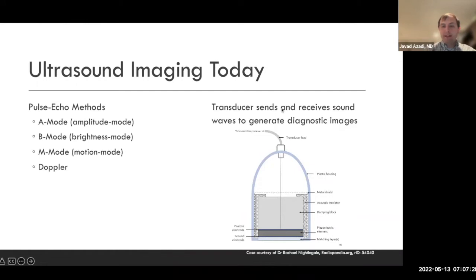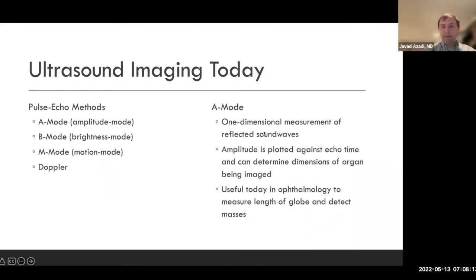The transducer both sends and receives sound waves to generate diagnostic images. This is just a schematic for what a generic ultrasound transducer looks like. It has a wire going to the actual probe, and that's to transmit and receive the sound waves. There's plastic housing. There's a dampening block to reduce the echoes posterior to the piezoelectric element. And then there's some matching layers. And basically what it's able to do is send echoes out, and then the echoes bounce back. They hit the piezoelectric element, and then they can be read out. The computer does all of the post-processing, and is able to give us real-time images.